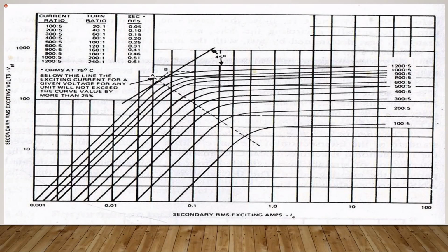Okay, sir. If you are using, say, the 600 to 5, yes? If you're using the 600 to 5 tap, which is here, then if you now have 2400 amperes on the primary, you'll get 20 amperes on the secondary. Yes, sir. Understood. So it's a tap that you're using. Okay. All right. Yes, Ms. Montague.